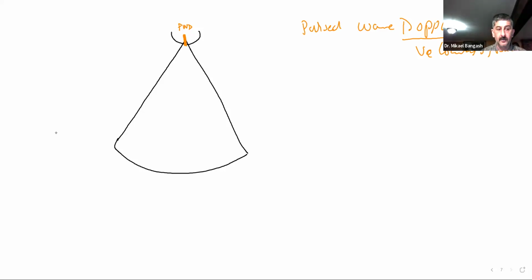Now, why do we call it pulsed wave? Why do we call it pulsed wave? Mainly because this PZT is alternatively going to be on, followed by a silence.